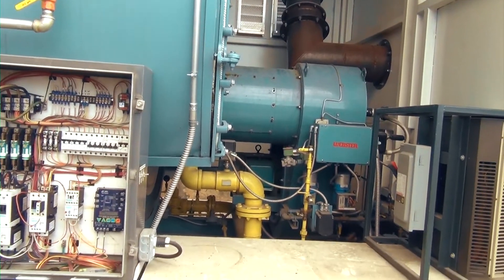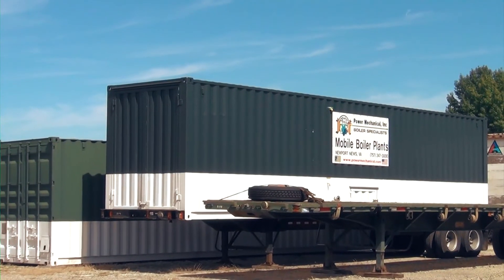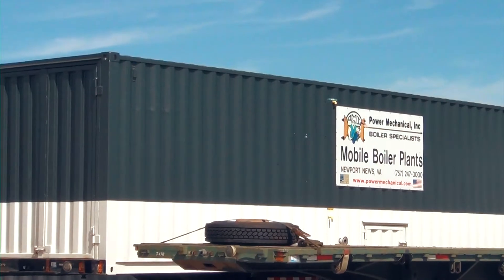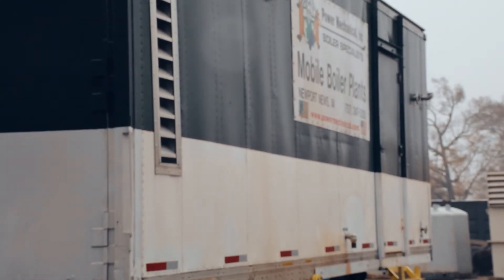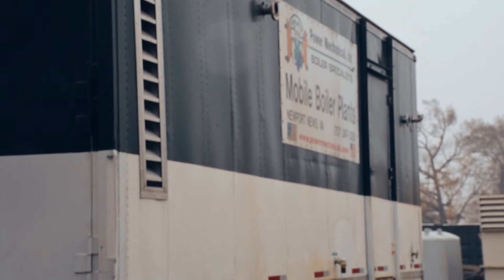This is something that can work in a crawl space or anything. Our enclosed mobile boilers are equipped with electric heaters sized accordingly to heat the enclosed space, especially areas around the DA and feed tank where it may not be getting the boiler's radiant heat. Usually there will be one in the front and one in the back, and you need to check these daily to make sure they are working properly. This is a primary line of defense for the freeze protection of your boiler.